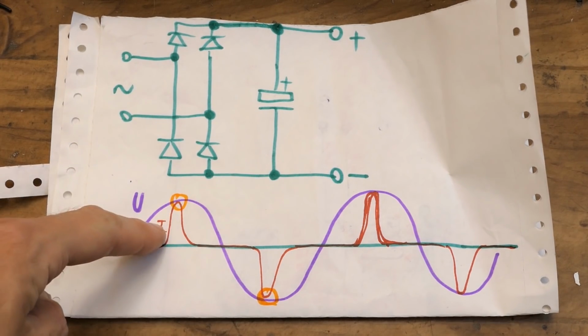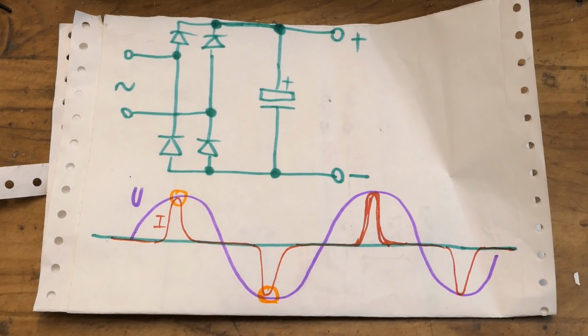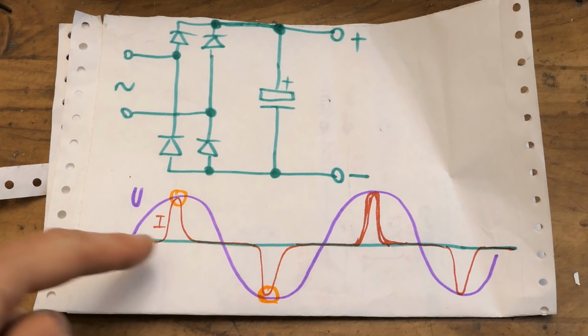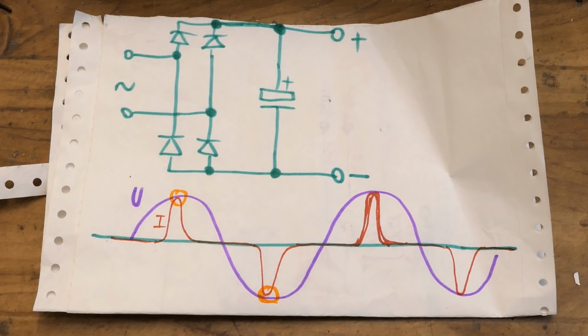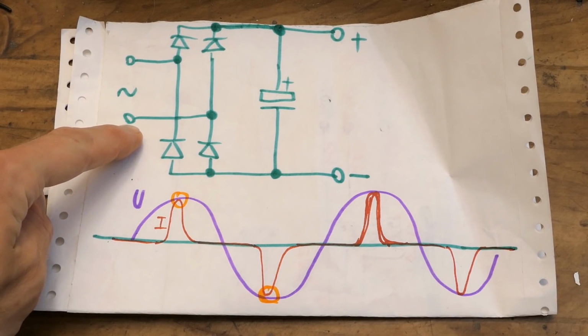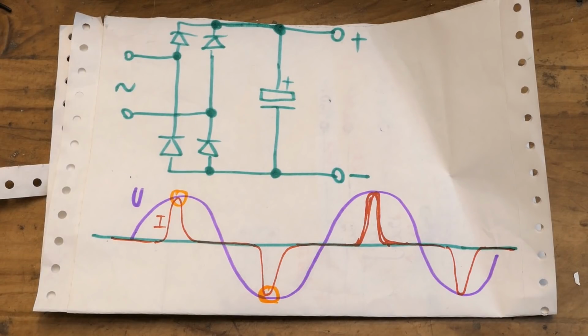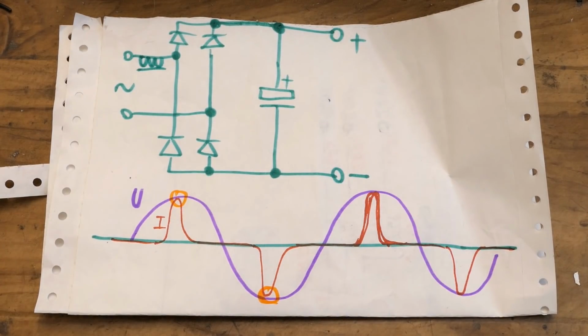But a low power factor based on a harmonic distortion is a bit harder to compensate than the low power factor caused by a phase shift. A harmonically distorted current cannot be solved by just adding a capacitor or inductor in parallel, and the power factor of switching power supplies or other loads with a rectifier at the input can be partially improved using a passive power factor correction, in the simplest form using just an inductor in series, but this only improves the power factor partially, not fully. It never brings it back to 1. To get the power factor of a rectifier close to 1, you need an active power factor correction, which involves a switching circuitry.